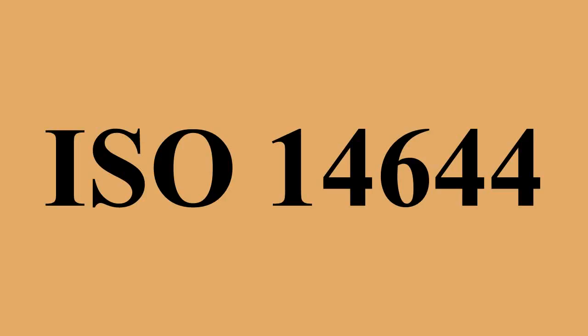Part 1 covers the classification of air cleanliness in clean rooms and associated controlled environments. Classification in accordance with this standard is specified and accomplished exclusively in terms of concentration of airborne particulates. The document was submitted as an American national standard and has been adopted as ANSI/IEST ISO 14644-1-1999 in the United States, following the cancellation of FED STD-209E.